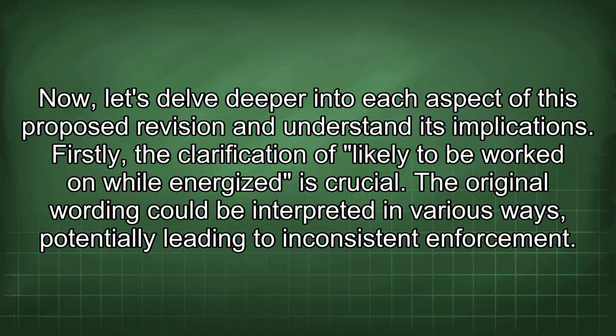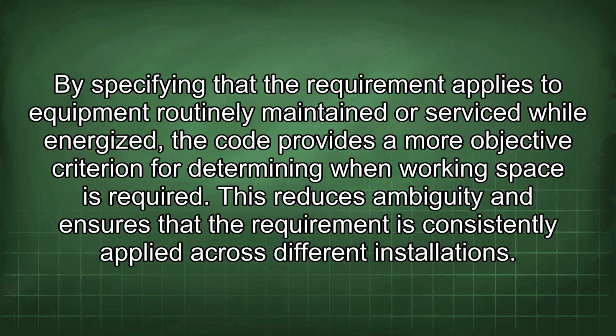Now, let's delve deeper into each aspect of this proposed revision and understand its implications. Firstly, the clarification of "likely to be worked on while energized" is crucial. The original wording could be interpreted in various ways, potentially leading to inconsistent enforcement. By specifying that the requirement applies to equipment routinely maintained or serviced while energized, the code provides a more objective criterion for determining when working space is required. This reduces ambiguity and ensures that the requirement is consistently applied across different installations.